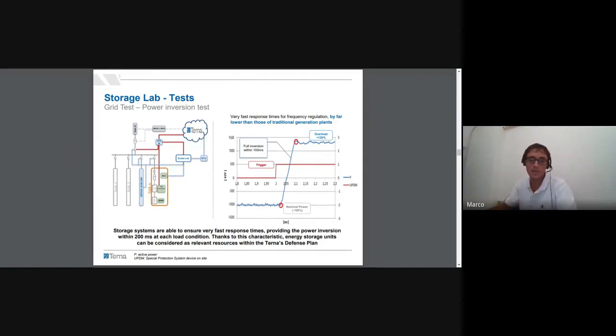We obtained from minus 100% up to 130%, so the full inversion of power within a time that, if I remember well, was 80 milliseconds. So less than 100 milliseconds we switched from minus 100 to 130, using an overload capacity of the energy storage system.